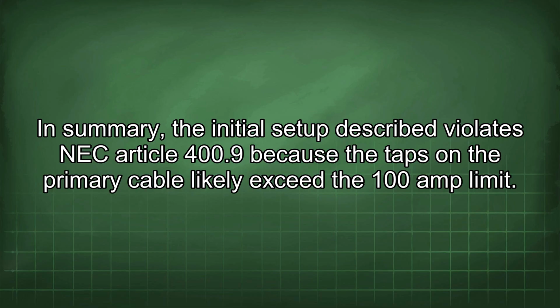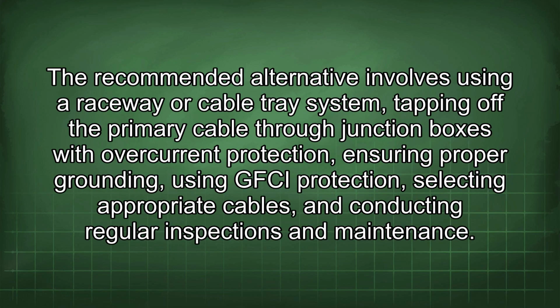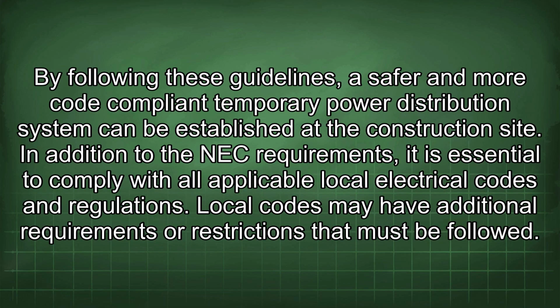In summary, the initial setup described violates NEC Article 400.9 because the taps on the primary cable likely exceed the 100 amp limit. The recommended alternative involves using a raceway or cable tray system, tapping off the primary cable through junction boxes with overcurrent protection, ensuring proper grounding, using GFCI protection, selecting appropriate cables, and conducting regular inspections and maintenance. By following these guidelines, a safer and more code-compliant temporary power distribution system can be established at the construction site.